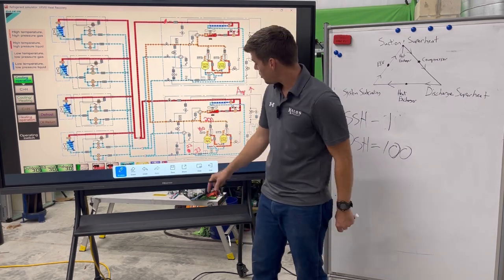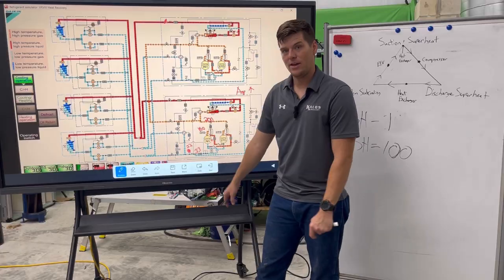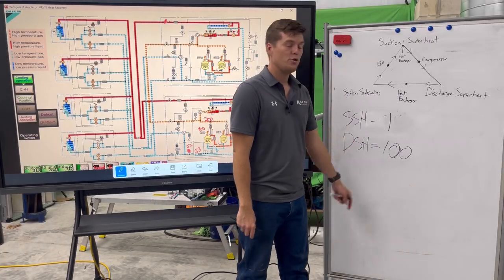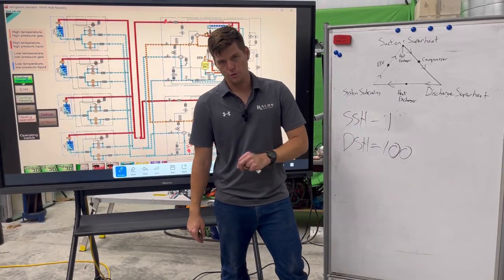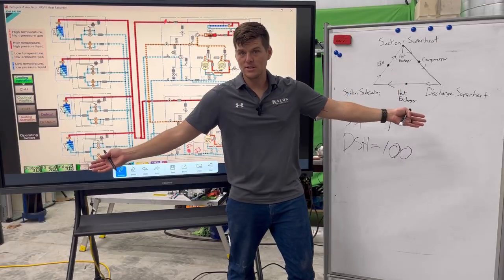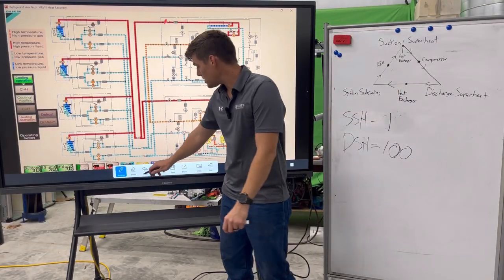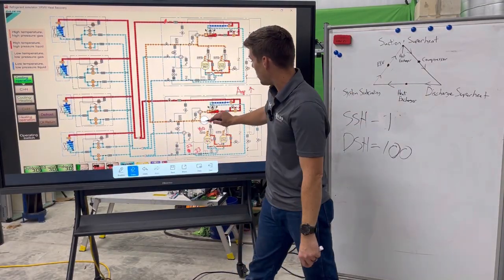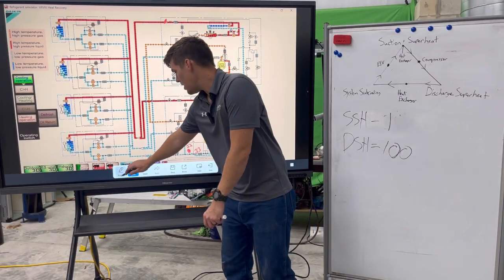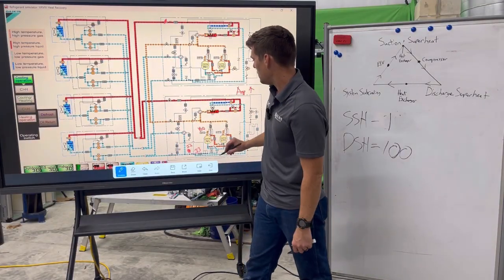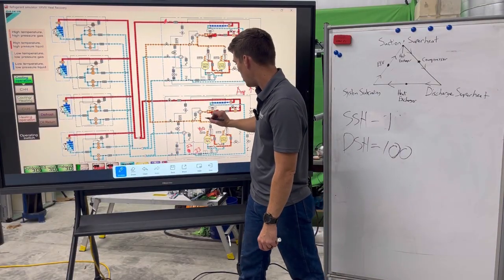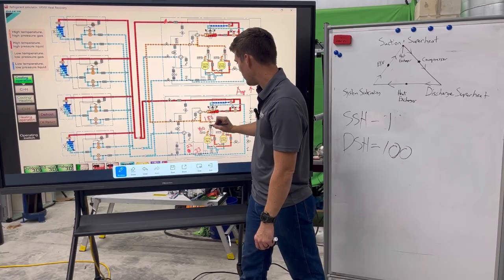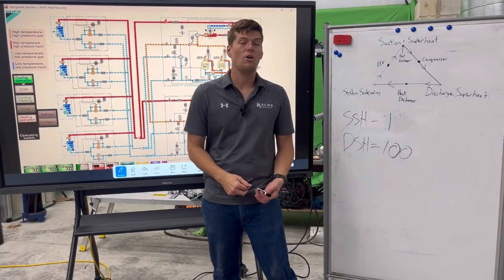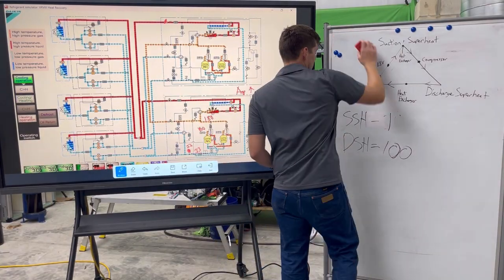Because again, I know that I'm getting liquid back, which is a bad thing, but then 2, my discharge superheat is through the roof. The difference? Lack of oil. Okay, so let's mix this up. Let's get rid of our 200 degree discharge temperature, and let's go with something maybe a little bit more reasonable, and let's do 180 degrees. You see 180 degree discharge lines all the time on VRF systems. So what does that put me at now?